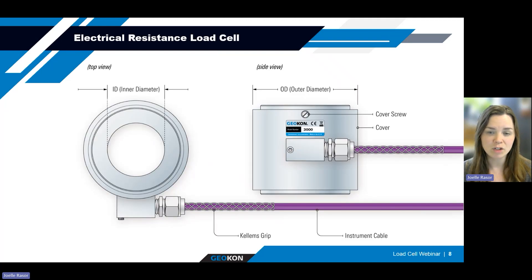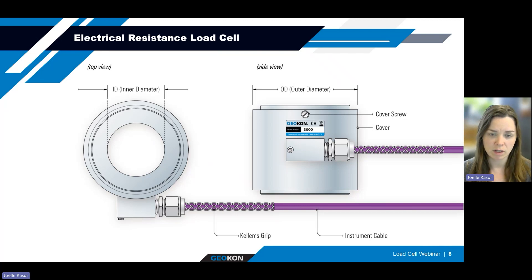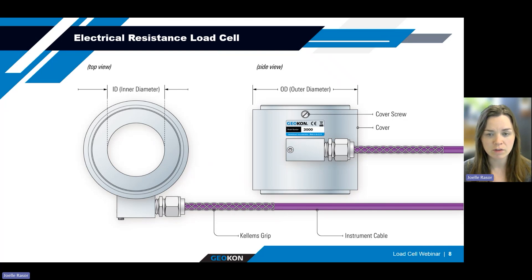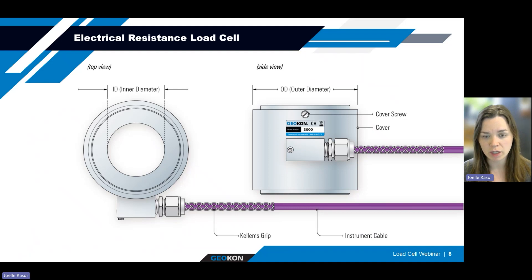The electrical resistance load cell is made from an annulus of high-strength steel or aluminum and is manufactured with 4 to 12 electrical resistance gauges in a Wheatstone bridge configuration, similar to the vibrating wire load cells. They can be manufactured with a solid body or hollow core to accommodate any equipment that needs to pass through the load cell. The electrical resistance strain gauges are etched onto the perimeter of the load cell body, and then a protective cover is permanently installed over the body. Readings from each strain gauge are averaged to compensate for eccentric loading. They are also designed according to the specifications of your project in terms of capacity, inner diameter, and outer diameter.